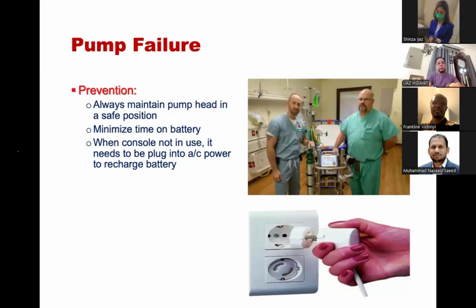Number two, your console should always have the backup support of the battery. If your battery is not properly charged, you have to make sure the AC power connection is connected to the AC supply, so you get a proper supply of current and your battery is fully charged, to avoid any volatile situations. When the console is not in use, it needs to be plugged into AC power to recharge the battery, and there are specific periods after which the batteries need to be replaced and charged.